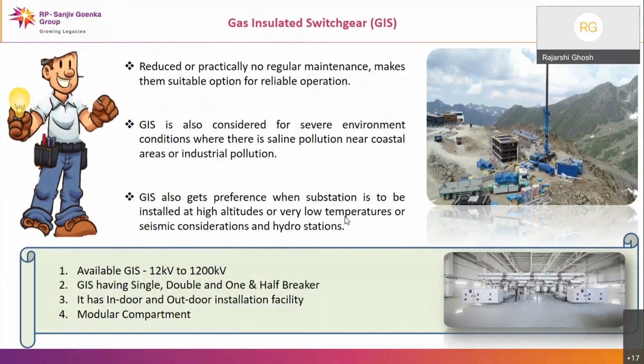Another advantage is that reduced or practically no regular maintenance is required. Almost everything is covered. Only the SF6 quality checking or a few dust cleaning tasks, small things, need to be done. GIS is also considered for severe environmental conditions where there is saline pollution near coastal areas. Since all the primary circuits are enclosed inside the SF6 chamber, the corrosion level is very less. So it is very easy to maintain in a corrosive atmosphere also. And GIS also gets preference when the substation is installed at very rough terrains or high altitudes, low temperatures, seismic considerations, hydro stations. GIS has a modular design, so it is easy to install, easy to shift, and so these are the advantages of GIS.